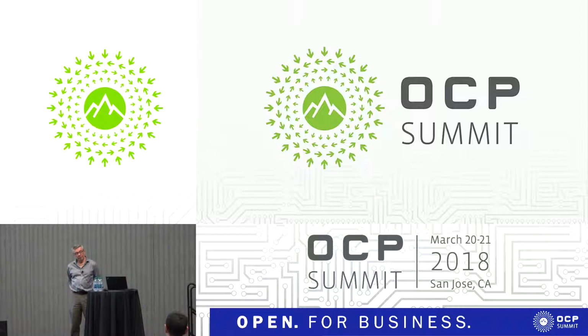Is this silicon based, or are you using wide bandgap technology within the power supply? I don't know, Ed. It's silicon. Silicon or silicon carbide, I think, is used in some of the devices, but it's silicon based. And how important in the future is it for you to increase your efficiency over 97? Well, we're always striving to improve efficiency. Once you get above 97, there's a certain amount of diminishing returns. When you look at the energy you're trying to save, it's fractional in terms of the heat generated. Yes, we're still striving for better, but it always comes at a cost. This industry is very cost sensitive, so there'll be a balance between energy savings and cost. When it really comes down to saving energy within the total building, the rectifier is not the culprit.